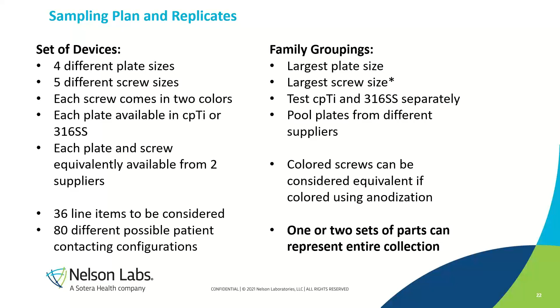Sometimes with sample availability, maybe with this plate set, you might actually offer the 2 largest. I don't think that's the end of the world. So again, in this example, we separated those into 2 different families, took the largest size from each. There, in this example, we separated titanium from stainless steel. Again, some might argue that that could be grouped due to cleanability of the device and the material. You might go back to the individual manufacturing processes and see if one is more worst case than the other. And then if you have 2 different devices that are different colors just due to anodization, I would certainly group those together.